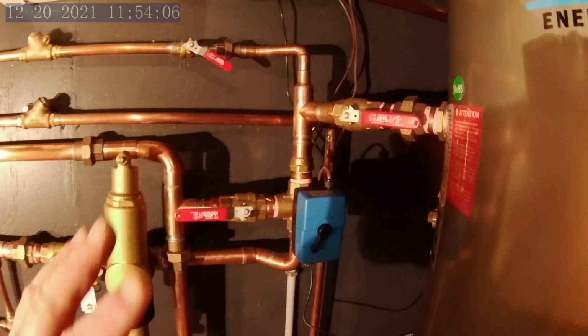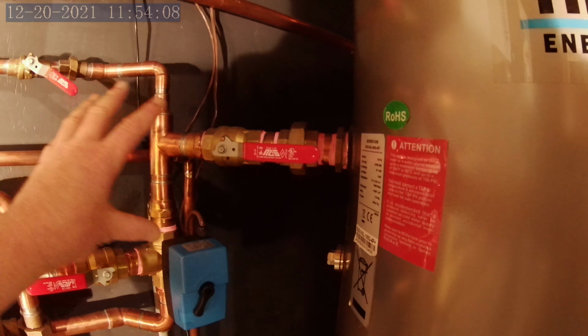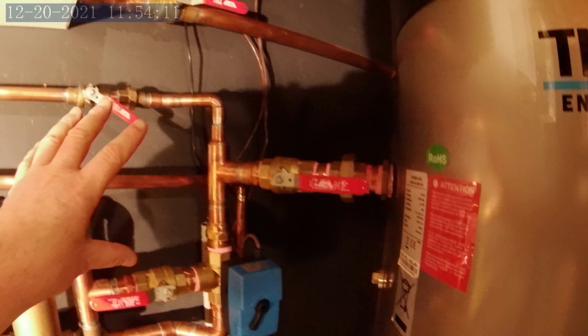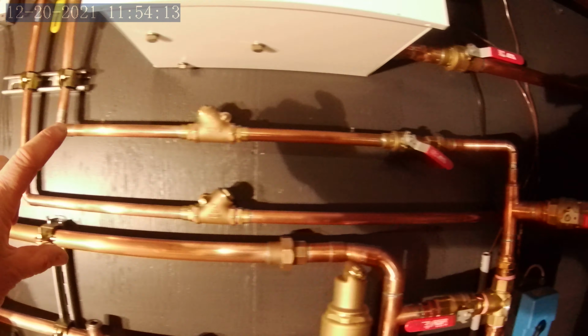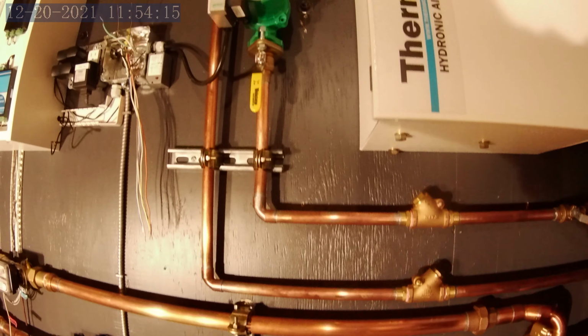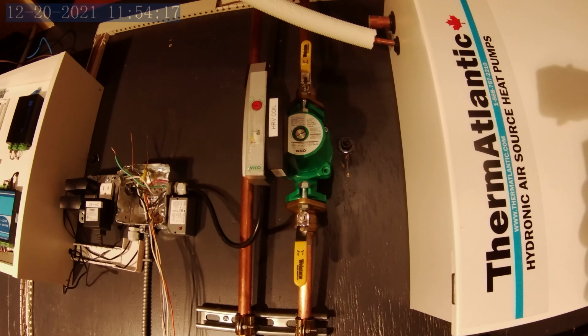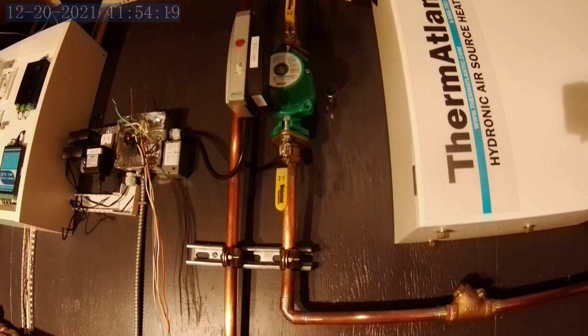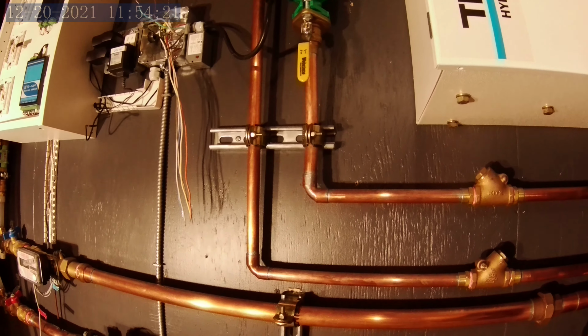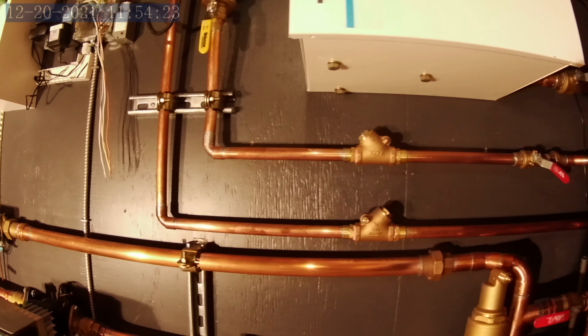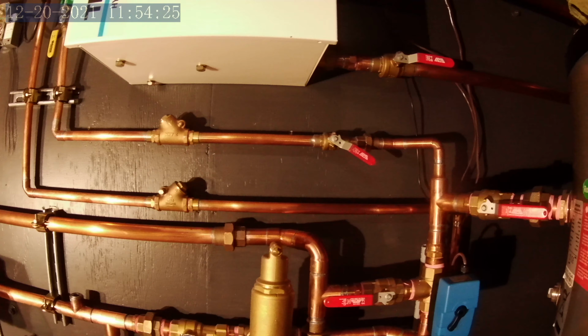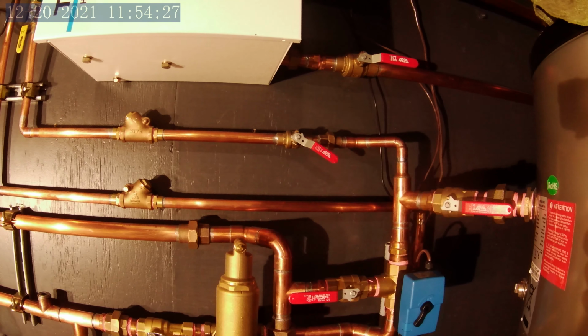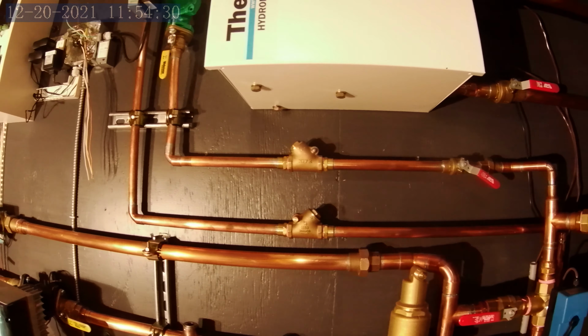I will have to worry about insulating the holding tank lines, as well as the lines going up to the HRV coil, and there's the circulator, because they will be, especially during the summertime, at tank temperature, which is, I think, going to be roughly 45 degrees Fahrenheit. So we will have to insulate these before next summer.